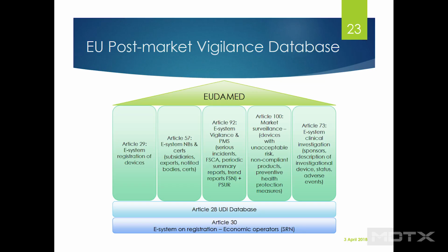UDI is to help standardize devices, to give them a coded system. So when you're talking about a product, instead of trying to describe the brand name of the product, you can punch in the UDI number, right? And of course, that UDI database has a lot of details about that product. So over time, this is going to make a big difference. Okay.